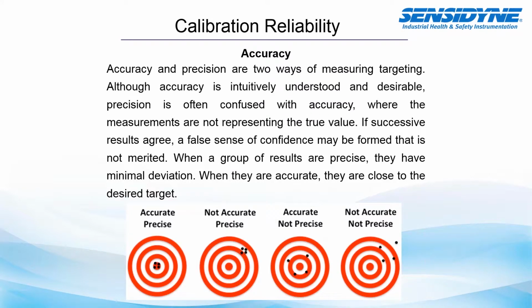Now, accuracy and precision are two different ways of measuring targeting. Although accuracy is intuitively understood and desirable, precision is often confused with accuracy, where the measurements are not representing the true value. If successive results agree, a false sense of confidence may be formed that is not merited. So basically, if you're looking at your calibration results and your live flow readings are coming up very close to each other, we might think that this is an accurate reading. However, this is really stating that the precision of the sample readings are very close together and tight. So you can be accurate, but not precise.